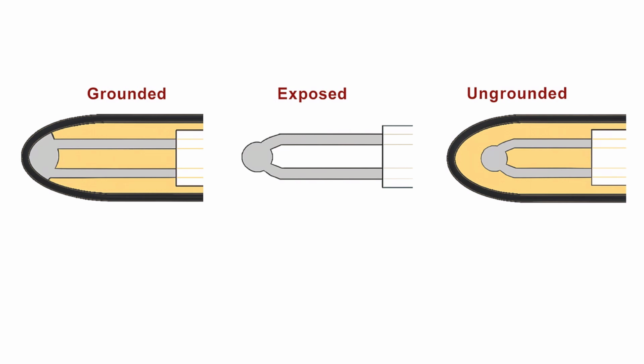Thermocouples can be built in several physical configurations depending on the environment. In an ungrounded type, the measuring junction is electrically isolated from the metal sheath, which prevents electrical interference. In a grounded type, the junction is welded to the sheath, giving a faster response time, ideal for measuring gases or liquids under pressure. And in an exposed junction, the wires are bare, giving the fastest response of all, though they are less protected from corrosion or mechanical damage.